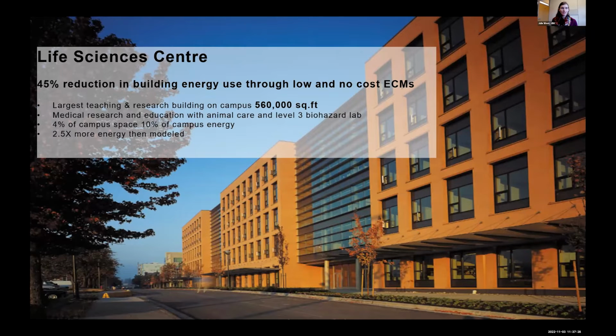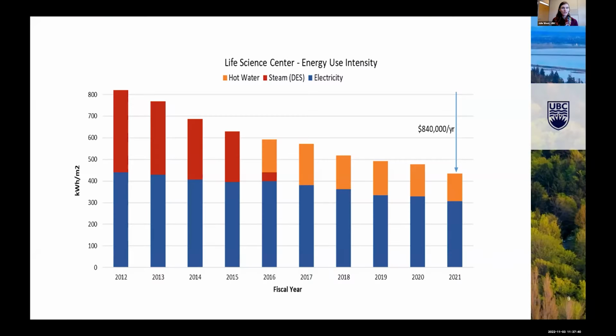When it was originally built, it used an exorbitant amount of energy, roughly 2.5 times more than was originally modeled by doing the LEED certification of it. And this graph gives you an idea of the energy use intensity. On the y-axis, we have kilowatt hours per square meter of energy consumption for the building. And then you can see throughout the fiscal years how we've been able to reduce that by roughly $840,000 a year.